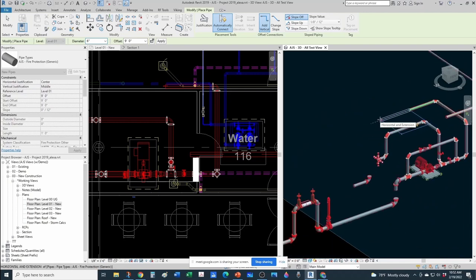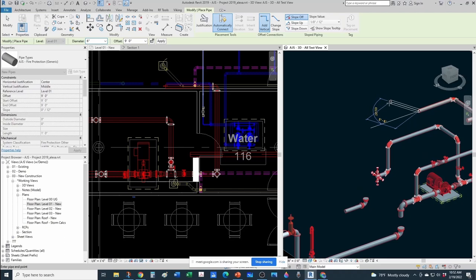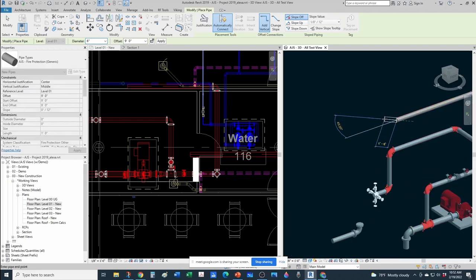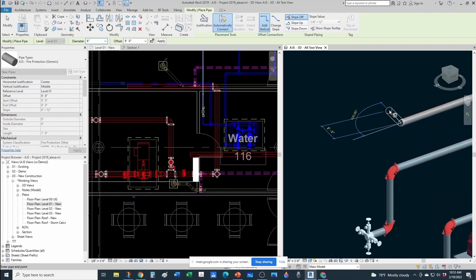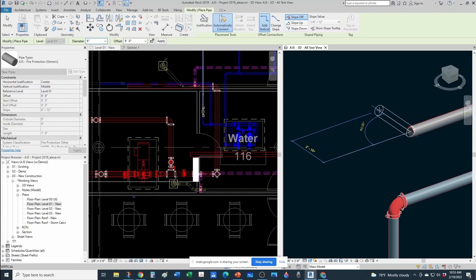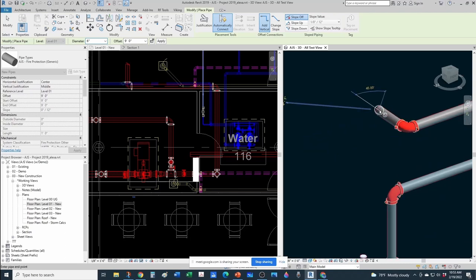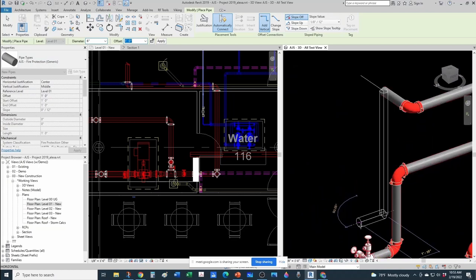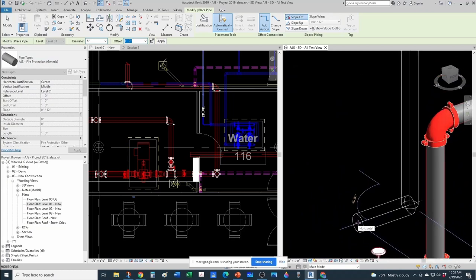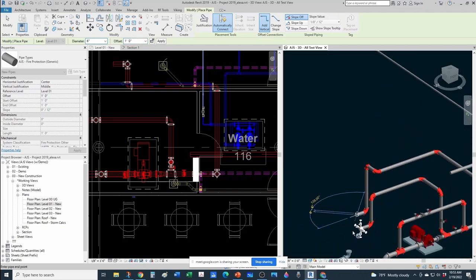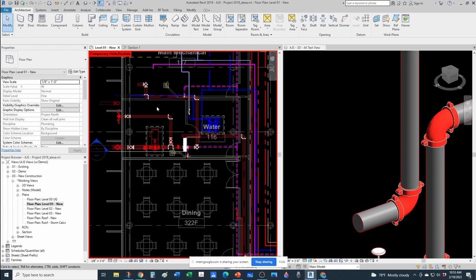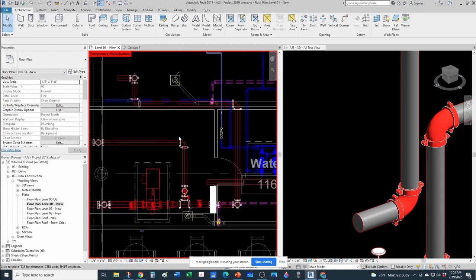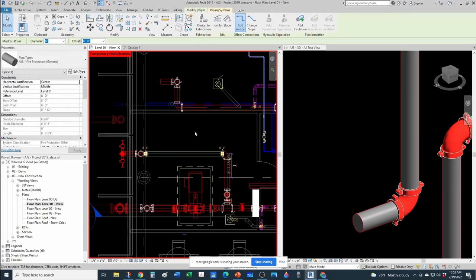I can get a little closer. Notice that I'm coming out of my room here, but I can adjust that. So here I can keep going, and I could probably do an offset because I want to have my pump controller somewhere here, and I don't want to have water on top of my controller. So let's plan for that offset here. And then we could come down to, let's say, 1 foot of elevation. Then we're coming out of our building, and then you go down underground. And you could have done this from the top view if you wanted to. In this case, my preference was to do it from the 3D view.